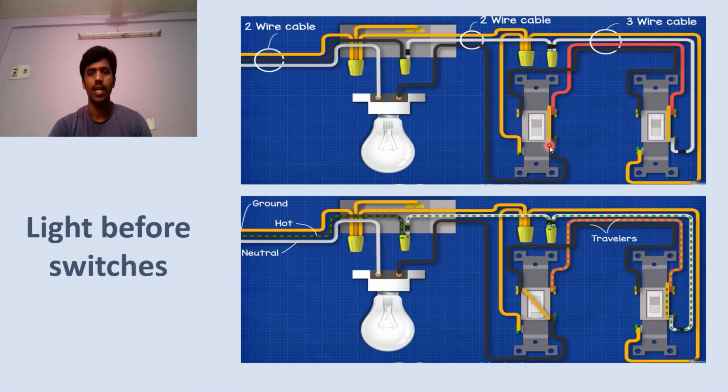And there is a connection from the common terminal of switch 1 given to the other terminal of the light fitting. And the ground terminal of switch 1 and switch 2 is given to the wire connector which in turn is connected to the wire connector which is present in the ceiling, and the output of this wire connector which is present in the ceiling is given to the screw which provides proper grounding to the whole connection.